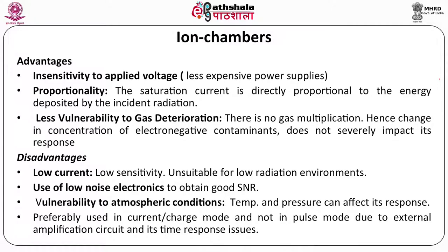In the ion chamber region, the voltage applied does not change the pulse height, meaning the detector is insensitive to applied voltage — translating into a less expensive power supply. The current produced by ionization is directly proportional to the energy deposited by the incident radiation, because all ions produced have been collected. This detector is also less vulnerable to gas deterioration, and changes in concentration of electronegative contaminants do not seriously impact its response.